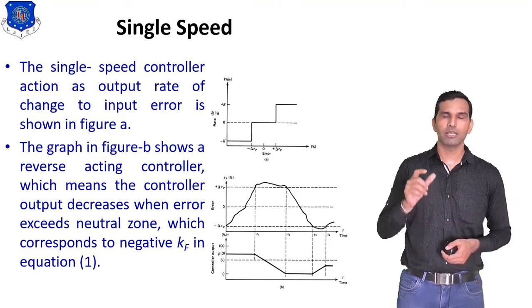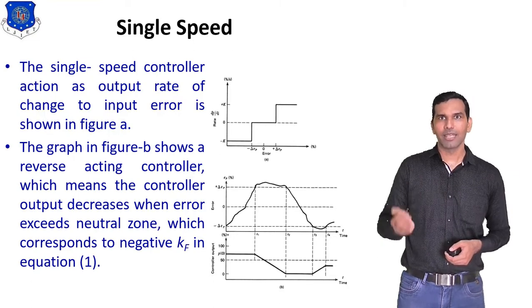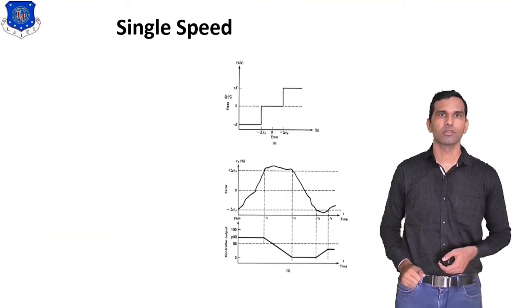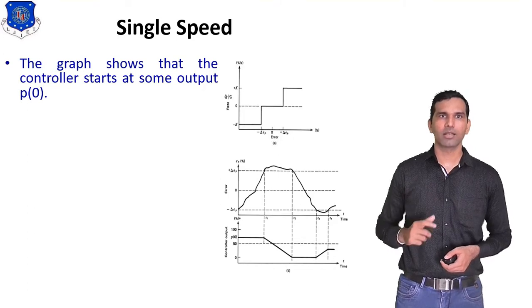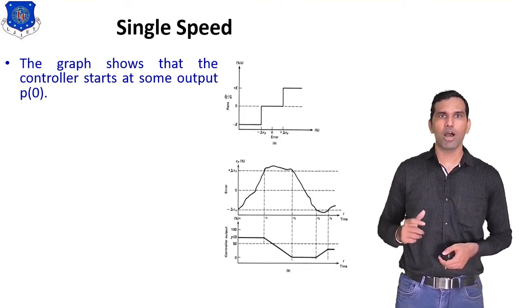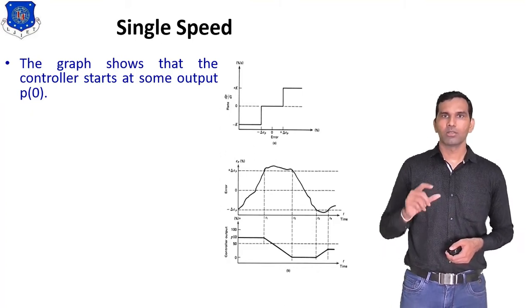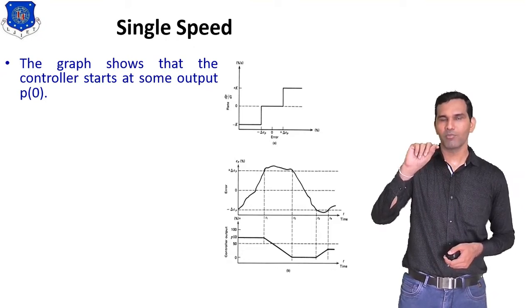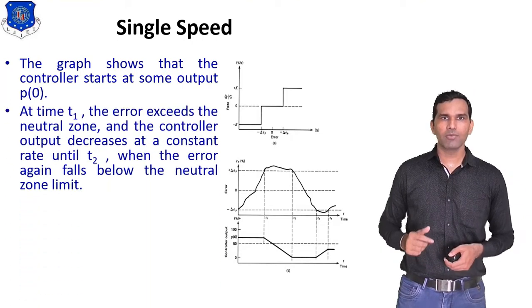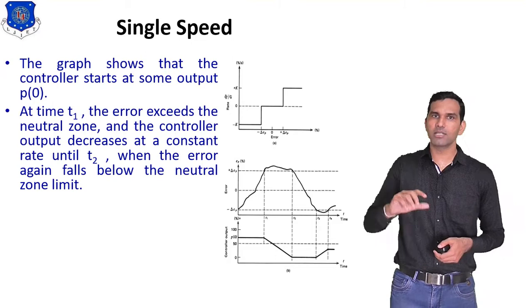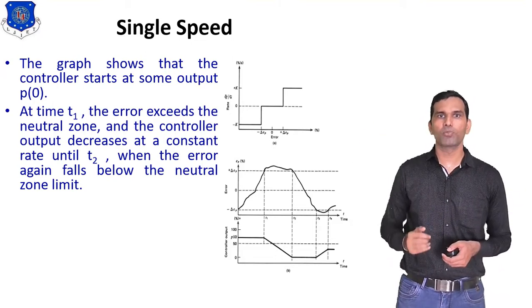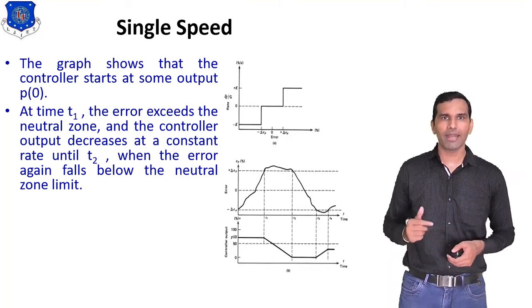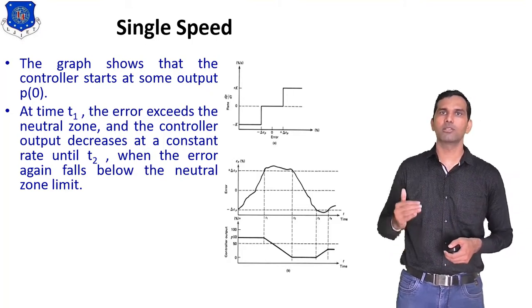In reverse action, when error is increased, the controller output is decreased. The graph shows that the controller starts at some output p₀. At time t1, the error exceeds the neutral zone, and the control output decreases at a constant rate until t2, where the error again falls below the neutral zone limit.